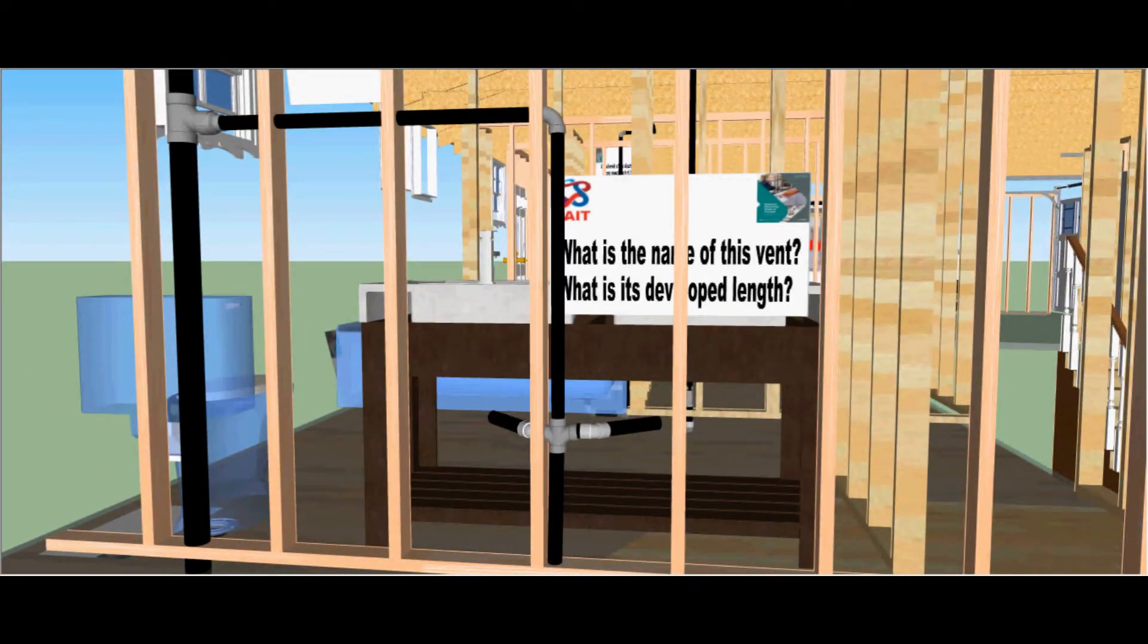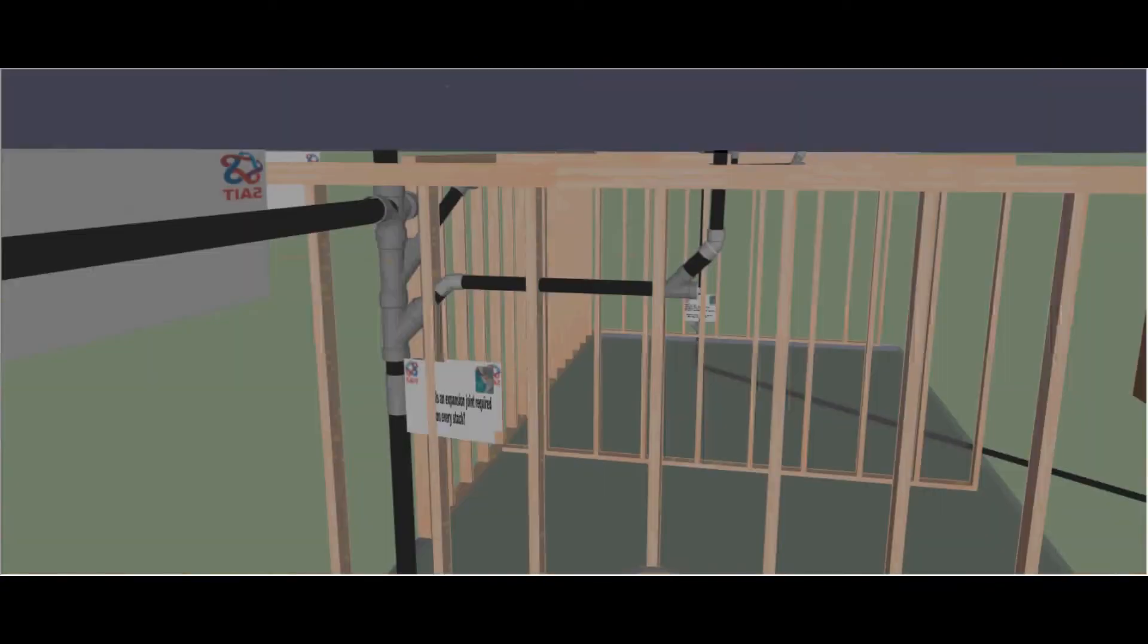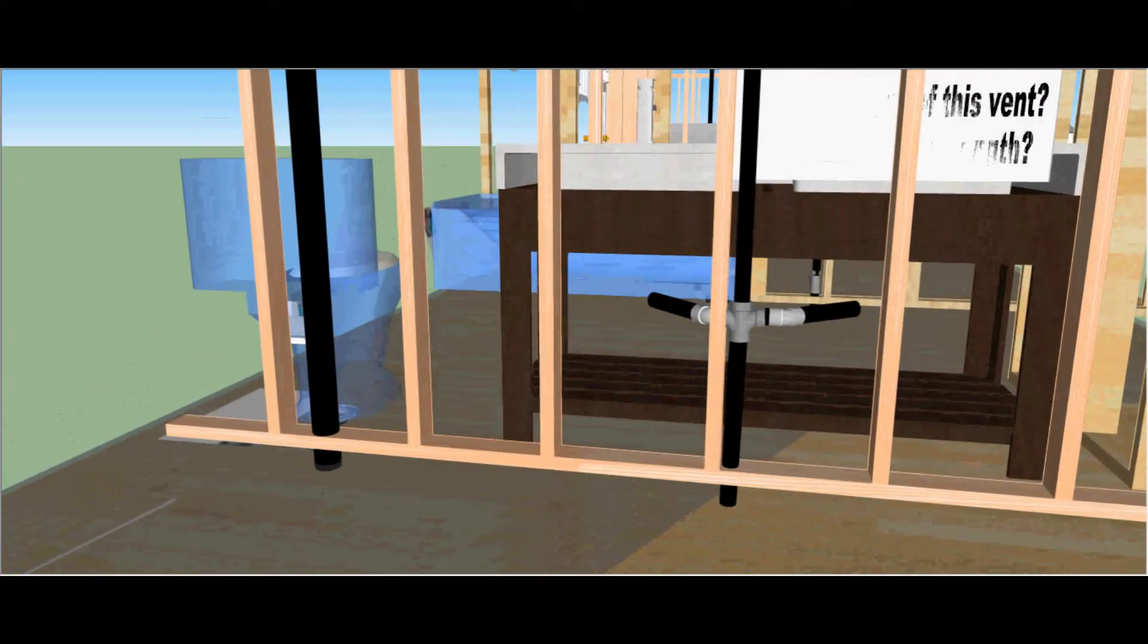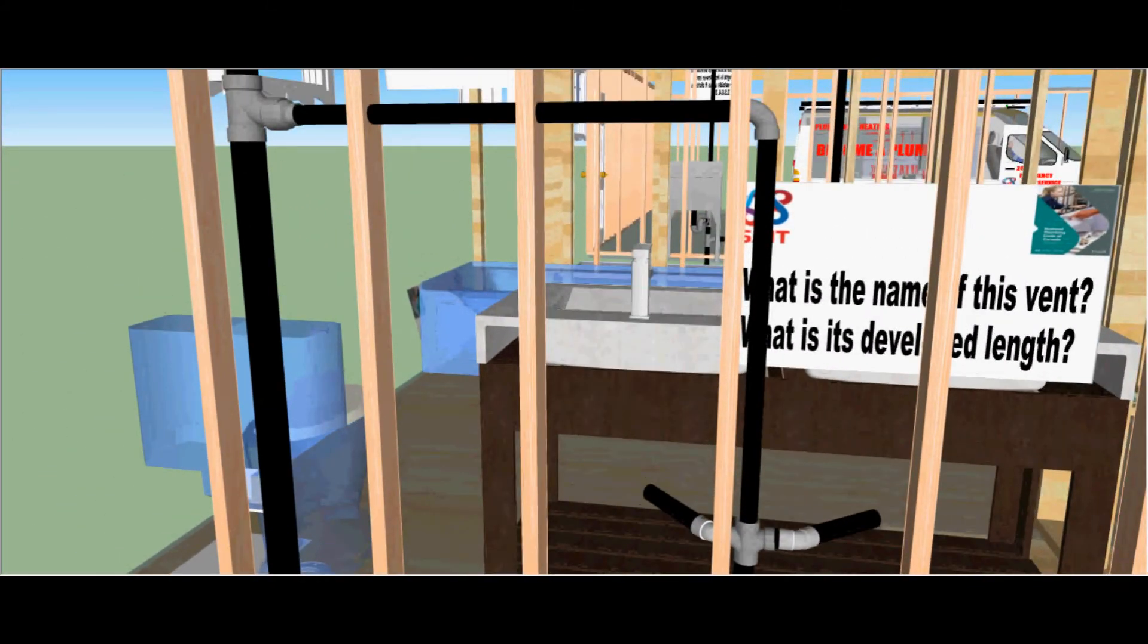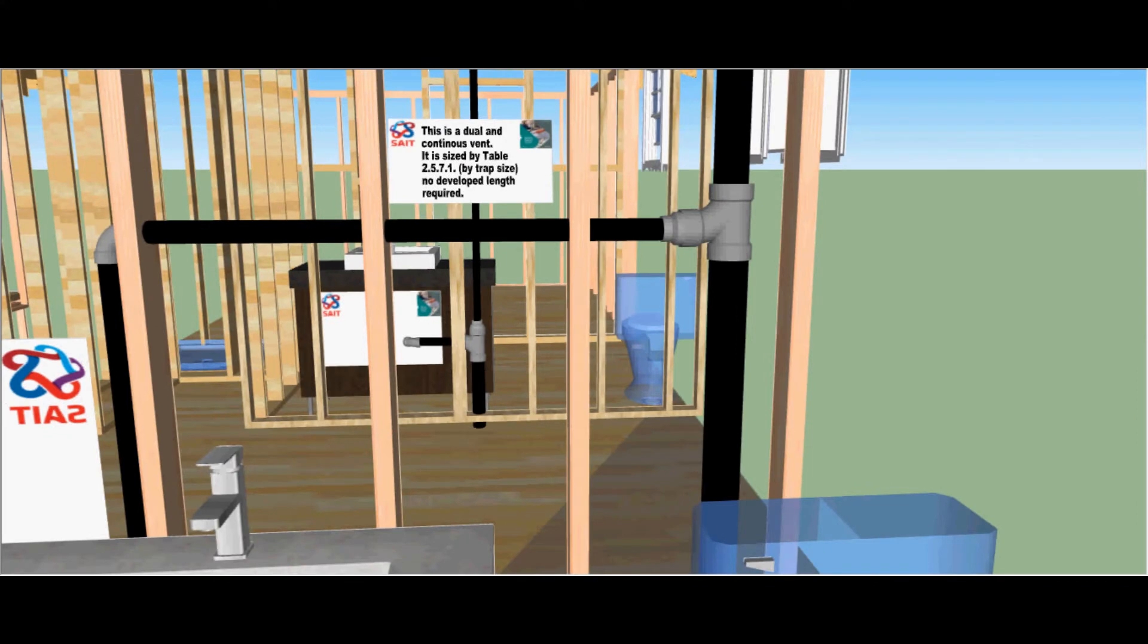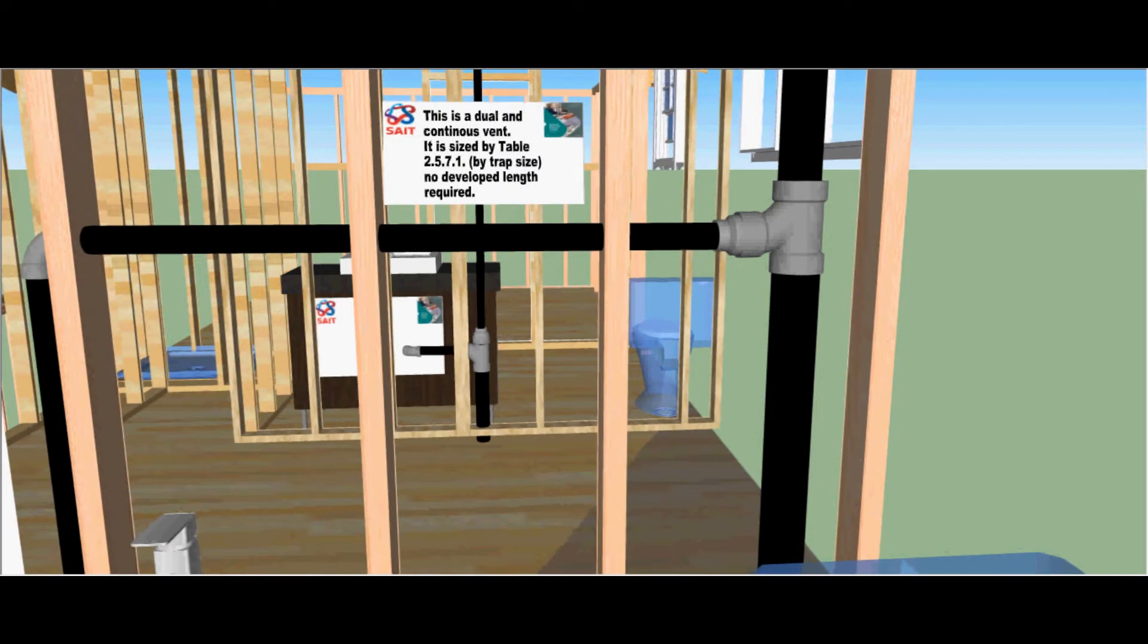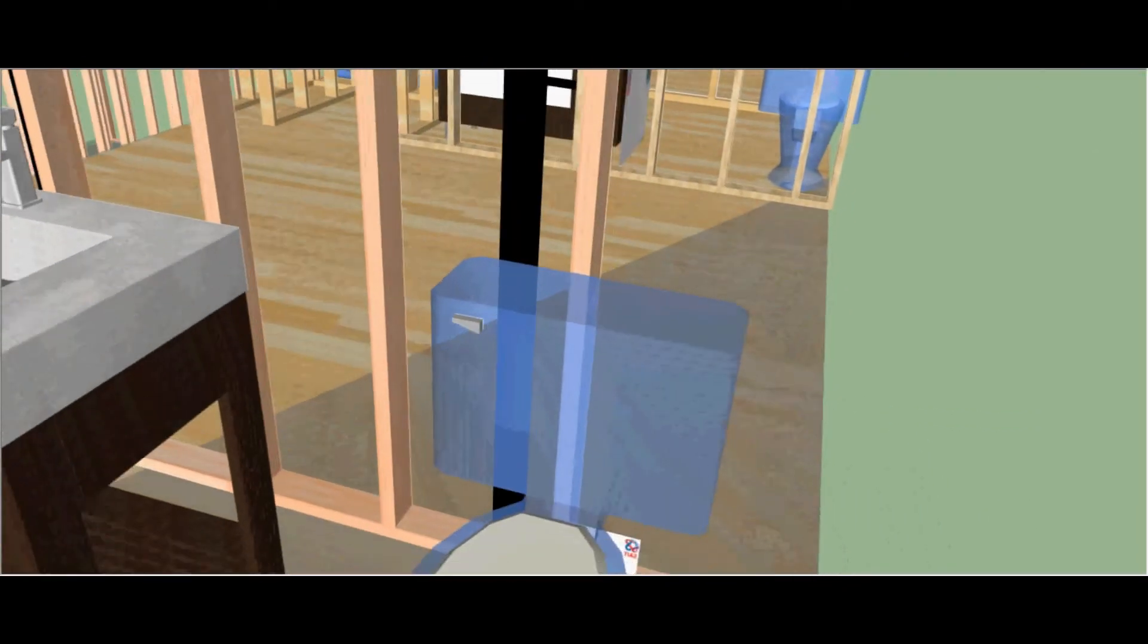What is the name of this vent? What is its developed length? As you can see it ties into the stack below the toilets. It has a vent that ties up above into the stack above. This is a dual continuous vent. It is sized by table 2571 by trap size. In this case no developed length is required on a dual or continuous vent or dual and continuous vent.